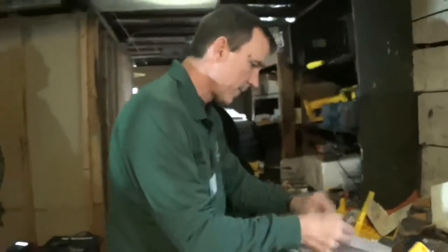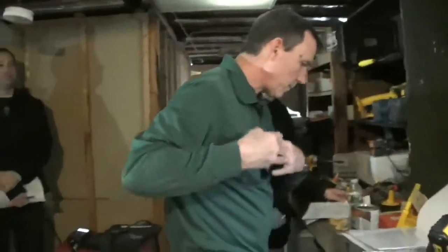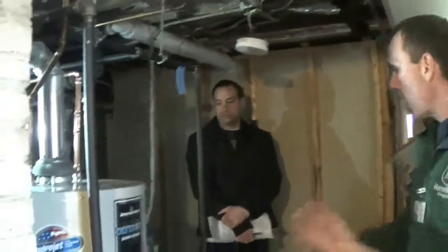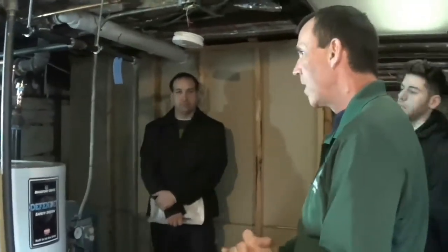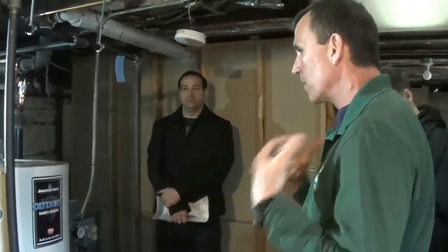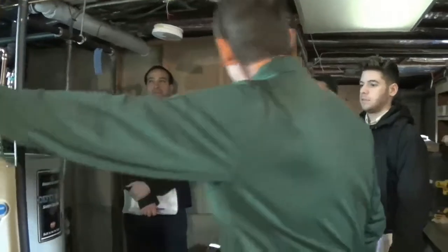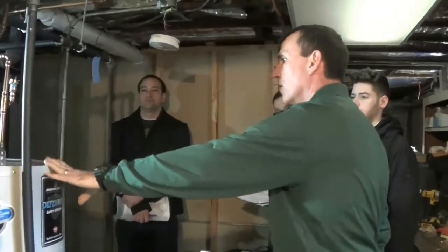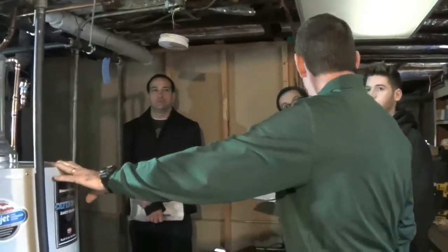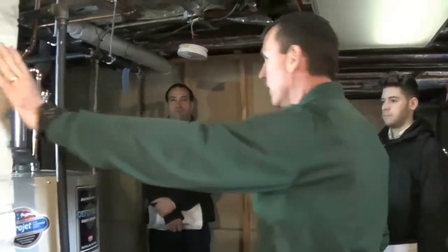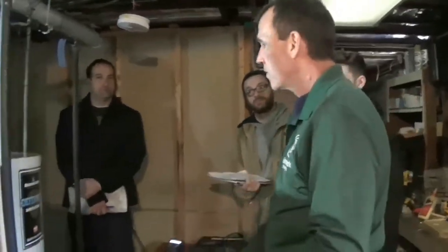So now I'm getting ready to test for spillage and draft on the smallest BTU per hour appliance, the one that is the smallest, meaning it doesn't do a very good job of heating the big masonry chimney up by itself. We start with this one first because if it's going to fail draft or spillage, it most likely would fail draft or spillage when it's at that disadvantage. It's the only thing going into the chimney. So we start there, and then we turn this off.